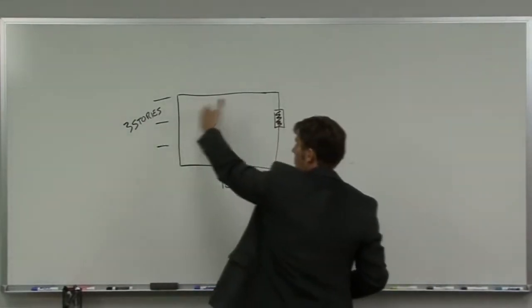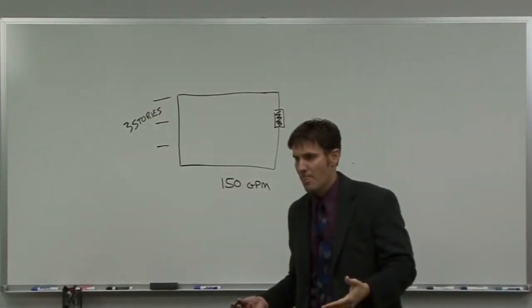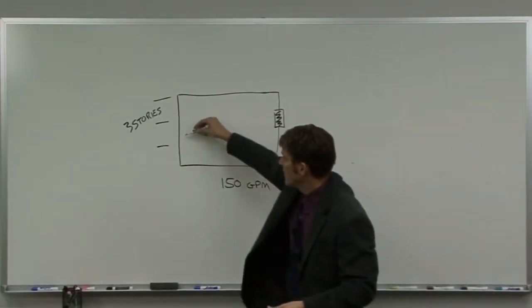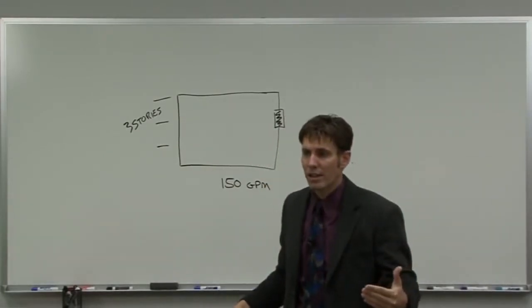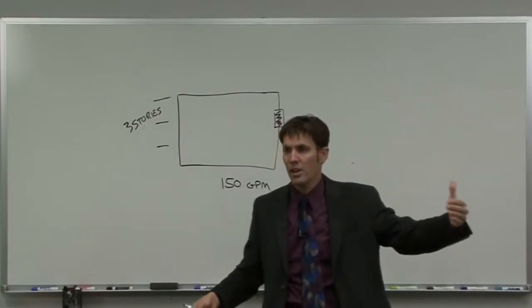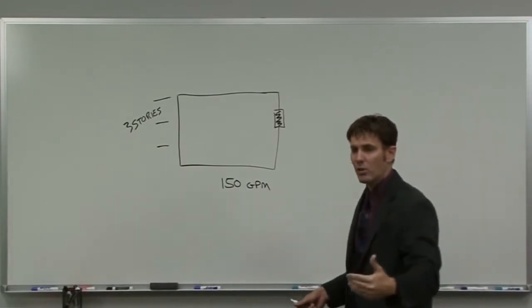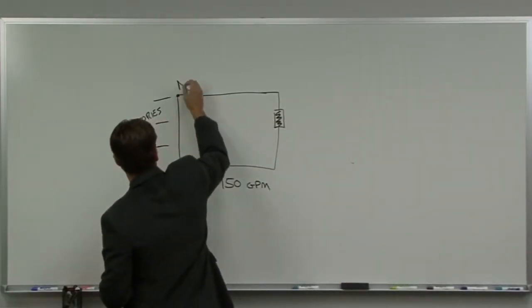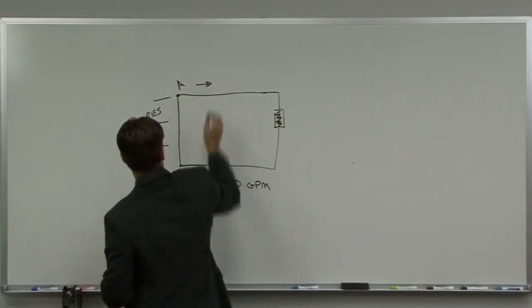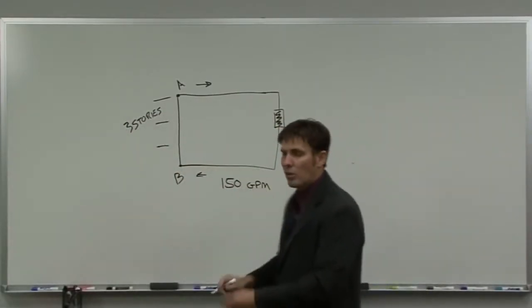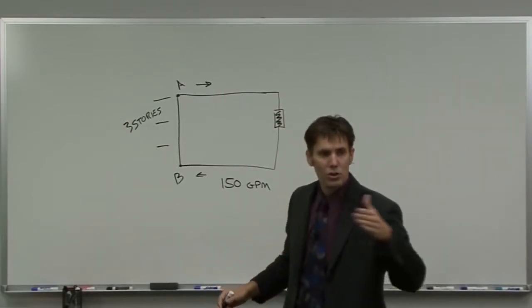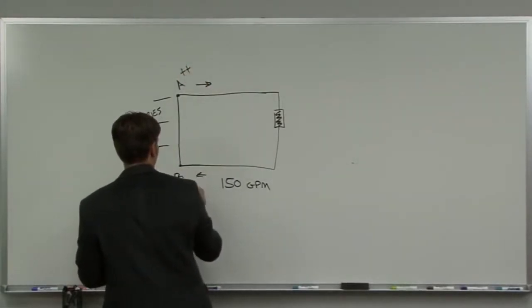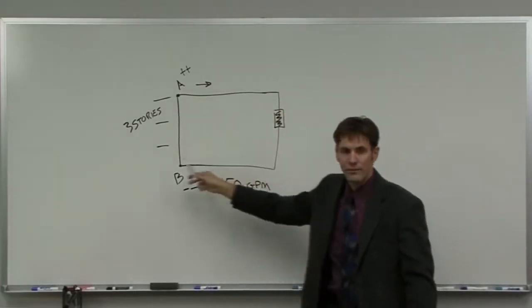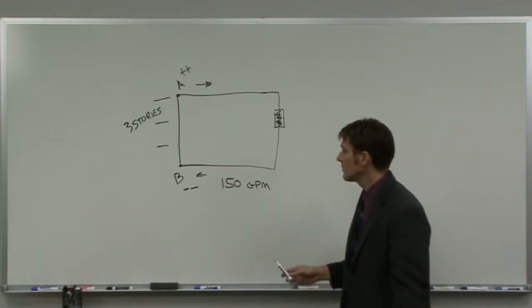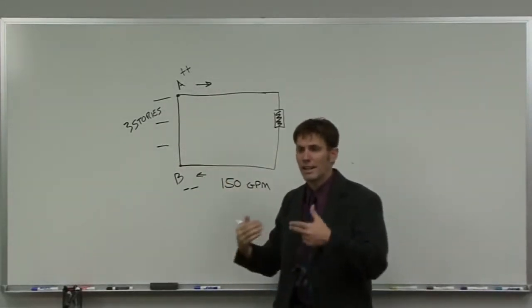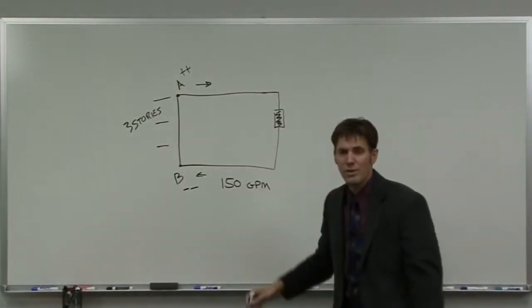So how do I get flow to move through a system? What creates flow? What it really boils down to is a change in pressure. If I want to move air through my ductwork, I have to change the pressure. When we have wind blowing outside, it's because we have changes in pressure. A change in pressure will create flow. So I've got to create a pressure difference from point A to point B. If I want to move water in this direction, then I've got to change the pressure. We always have a flow from a high pressure to a low pressure. So if I have a higher pressure here and a lower pressure here, then I will have flow in this direction. So that's what we're trying to accomplish in a hydronic heating or cooling system, is create a change in pressure between these 2 points so that my liquid will move in the direction that I want it to move in. Well, how do we do that? How do we change the pressure?